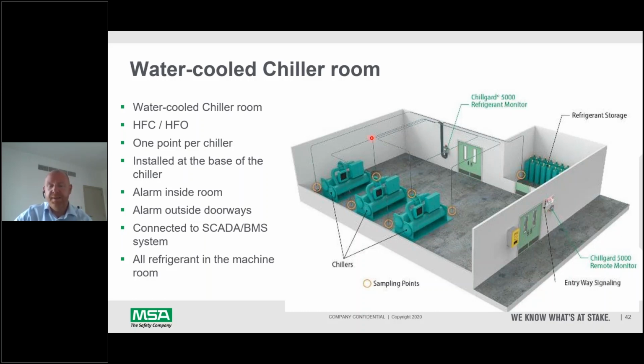And this is an enclosed space. So anything that leaks in a water-cooled chiller room will stay in the room, because the refrigerant stays in the room. Only water goes in and out. So one or two points per chiller at least, installed at the base of the chiller. Then we need to have an alarm inside the room, and we need to have an alarm at the doorways as well. And what ASHRAE calls for is some self-contained breathing apparatus as well, so that if somebody is unconscious, somebody needs to wear that apparatus in order to retrieve that person outside.